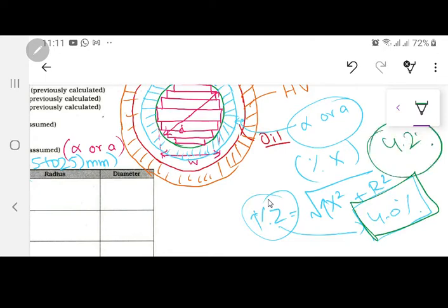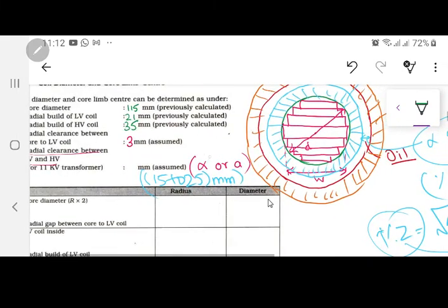Okay, while designing, at the end your no-load losses are fine, your copper losses are fine, but percentage Z comes out to be 4.2. Now, this is a very slight variation from your required value. So what you will do is play with this alpha or A variable, decrease that variable, and then see what the percentage Z is. The percentage X formula directly has this alpha or A as a parameter. We will come to that proof maybe next week, but percentage X is directly dependent upon this alpha or A.